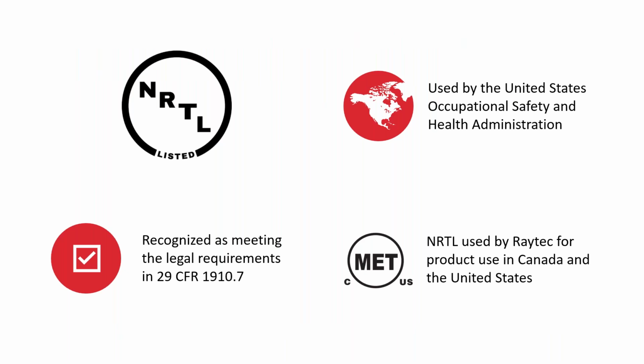The circle, which you can see, contains a certifying agency identity, product safety certification in North America. The C outside the circle indicates the product was certified by a Standards Council of Canada accredited certification body, and the US outside the circle indicates the product was certified by an OSHA approved NRTL for the United States.